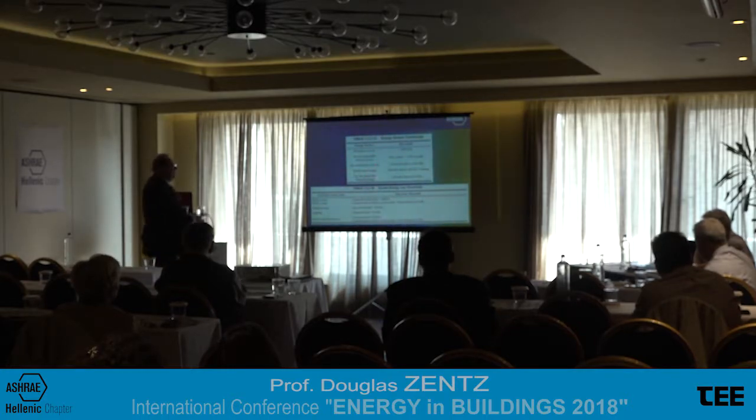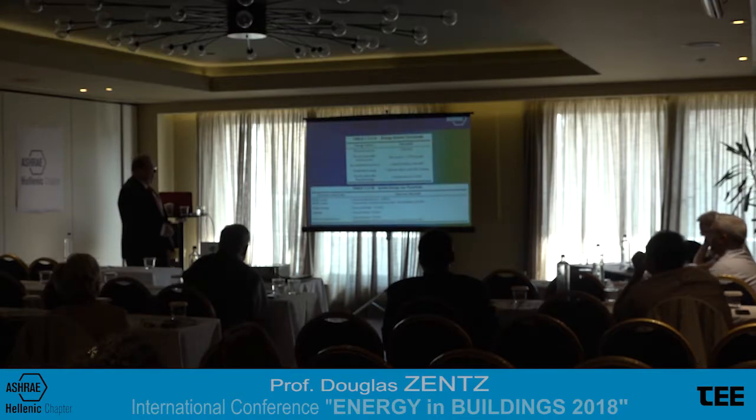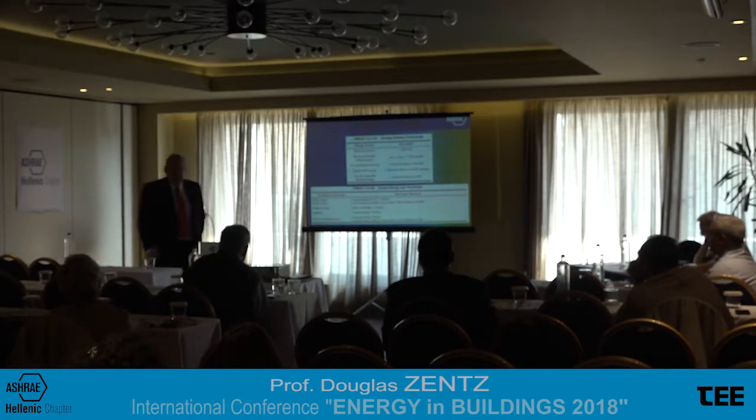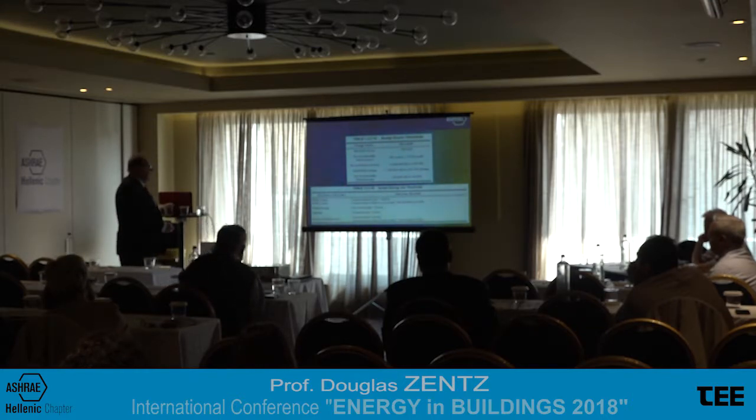Specific items have to be metered. Your on-site electrical source, and then also any specialized, like in the HVAC world, any device that's more than 100 kVA. There's a lot of things that are more than 100 kVA. If you've got a big building with big chillers, chances are your big chillers are more than 100 kVA. So there are many things that have to be metered. People moving systems and lighting systems have to have their own independent metering.